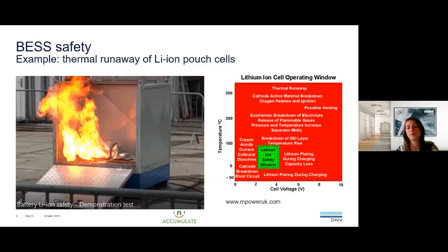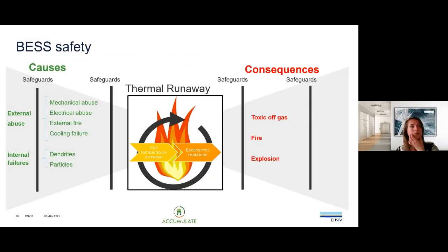So there's a specific safety window, which we already discussed, so I'll quickly run through it. We have the causes: internal failures and external abuse. So mechanical abuse like dropping it, electrical abuse like overcharging, external fires, or failures in cooling - that's the thermal abuse that can start a thermal runaway, where you can include multiple safeguards in your safety strategy.